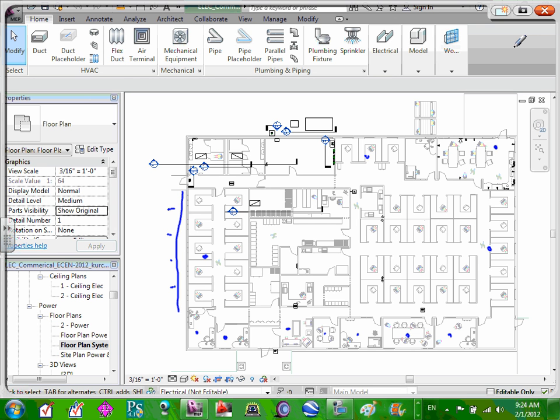I guess what we have and what we're requesting, you want it to be able to be heard throughout all of the space. They're pretty loud, and there's no real requirement that says it needs to be heard. So what I would say, if I was designing a security system, I would put maybe one for the open office here, and then maybe another one somewhere over here, maybe almost right there. I don't want it to be hidden away over a cube, but something to get that audible alarm out into the open spaces.